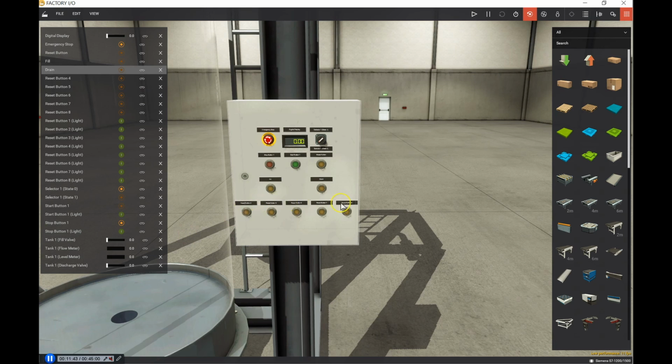Okay, and then these are all going to be my different percentages here. So I'm going to do reset push button number 4, double left clicking, putting 0 space %, enter. I'm just following through on each of these guys, double left clicking, selecting everything. This guy is going to be 25%. Enter. If you're not seeing those values change on the Lamicoid above the push button, you forgot to press enter. Next guy is going to be 75. Enter. And this final reset push button is now going to be 100%.